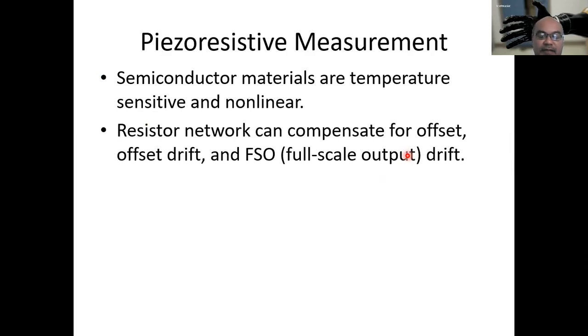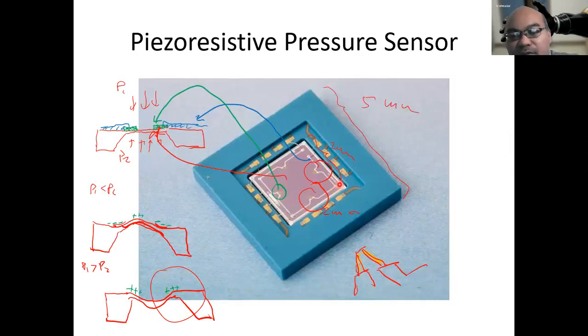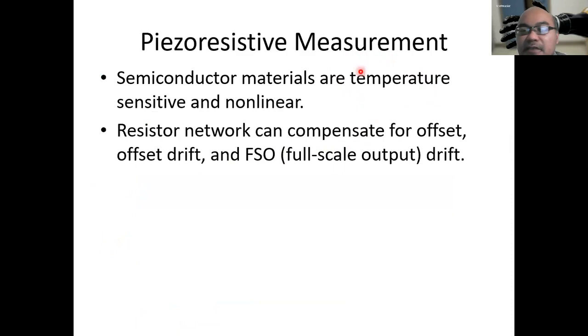That is why usually, in order to reduce or eliminate the effect of temperature, we also put not only here, but also this same kind of device somewhere outside, where it will also change due to temperature change, but will not be affected by the pressure change. So that it can compensate the temperature sensitivity of that piezoresistive device.